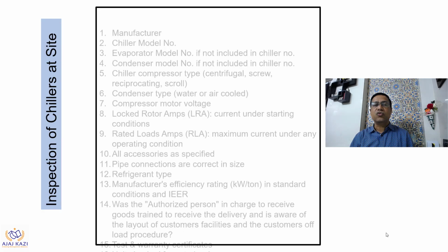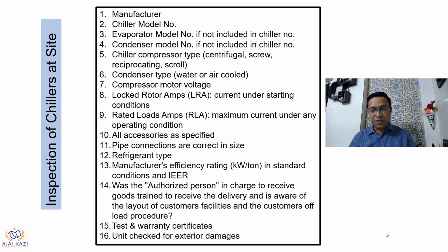Let's start with what we are going to check. So, inspection of chillers at site. First we need to check the manufacturer: who is the approved manufacturer, and who has supplied the actual material. Is there any gap? Yes, you need to check. Then the chiller model number. The model number which was approved and the model number which is delivered at site need to match. There should not be any difference. So that needs to be checked.